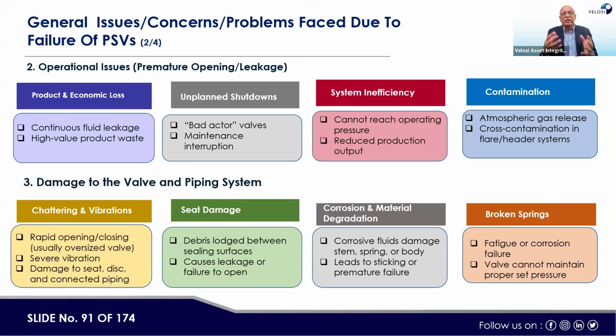Right, sir? So these are the scenarios where we see product and economical loss, unplanned shutdown, system inefficiency, and it may cause contamination as well. Then damage to the valve and piping system. So how may the PSV have a problem? It could be chattering and vibration, like rapid opening and closing, severe vibration, damage to seat and disc and connected piping. There could be a problem.